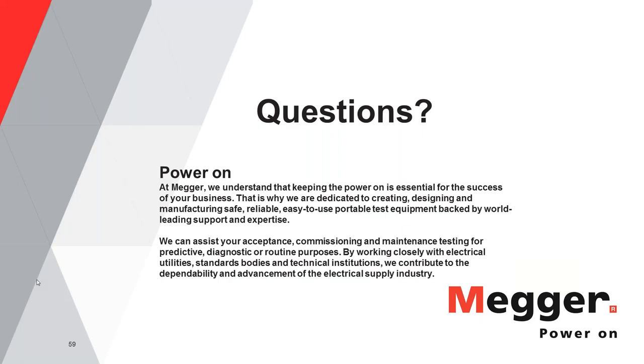Okay, the next question is, should we read peak or RMS for instantaneous tests? That depends on the trip unit of the breaker. As I said earlier, some trip units respond to the peak value of the current, some trip units take samples of the current signal and measure the true RMS. So if you want to do the test the right way, look at how the trip unit measures the current and select the acquisition method accordingly.